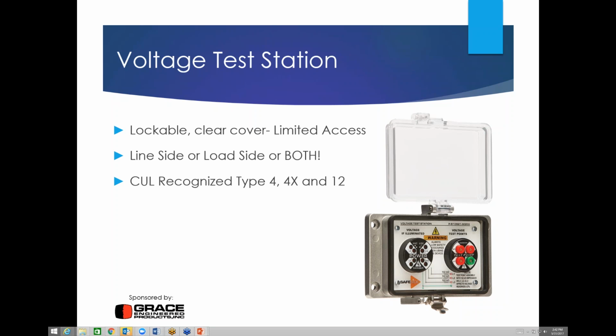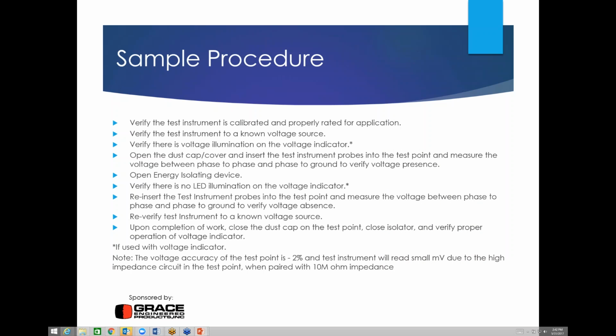And here's an example of a typical sample procedure. And that would be, again, as we talked about, verify that the test instrument is calibrated and properly rated for the application. If you are using the voltage indicator, verify the test instrument to a known source to make sure that it is working. Verify that there's illumination on the voltage indicator, and then open the dust cap or the cover, depending on if you're using it with the voltage test station. Insert the instrument probes or the test probes and measure that there's voltage present.